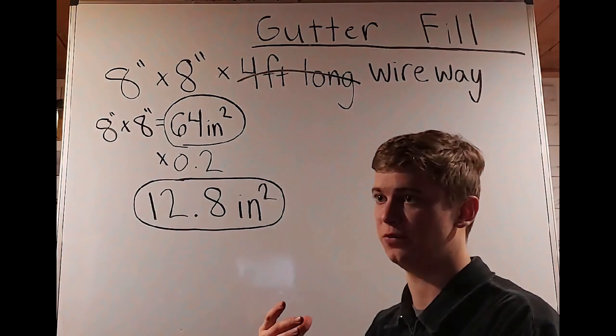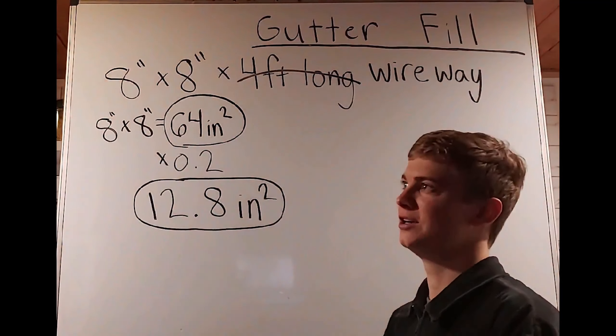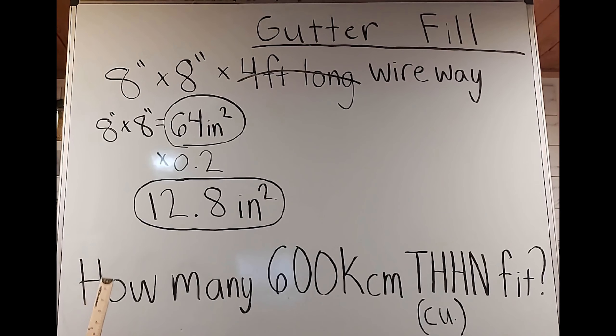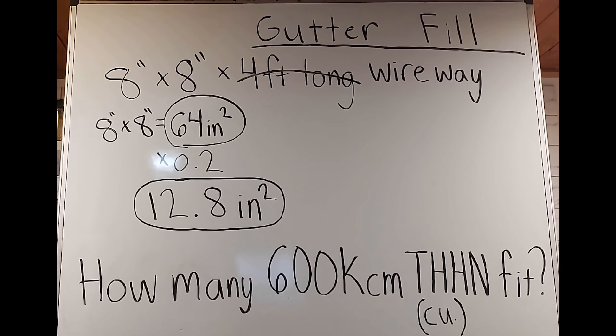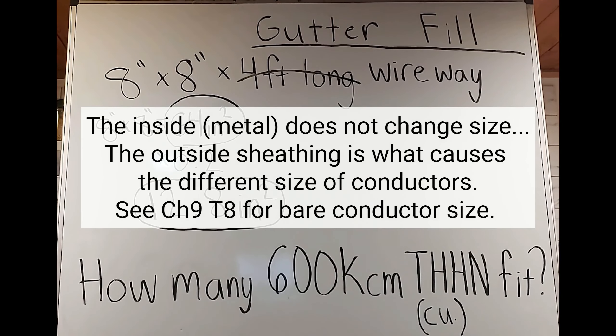The second part goes into what if we wanted to fill this with actual wires. How many 600 KCMIL THHN will fit in the 12.8 square inch space? This is copper. Oftentimes they'll mention copper or aluminum. When we know the wire type — THHN — and the size — 600 KCMIL — and we go into the table, we'll see it doesn't mention copper or aluminum, because the wire type already tells us what type of wire we're using. Aluminum and copper conductors of the same gauge can have the same square-inch area.